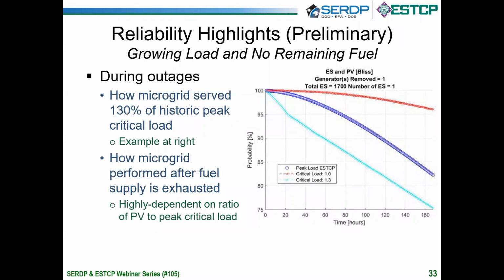The other reliability scenario we tested was what happens after the on-installation fuel supply is exhausted during the power outage. If you have no battery to store or meet out power from a PV system, there's virtually zero coverage of critical loads if you don't have diesel fuel. When you have batteries connected to your microgrid, we tested how long 100% or 130% of critical loads could be served. What the investigators found was that in many cases, those loads could be served for 24 or more hours at 95% or higher reliability. But in others, the coverage lasted only a few hours.